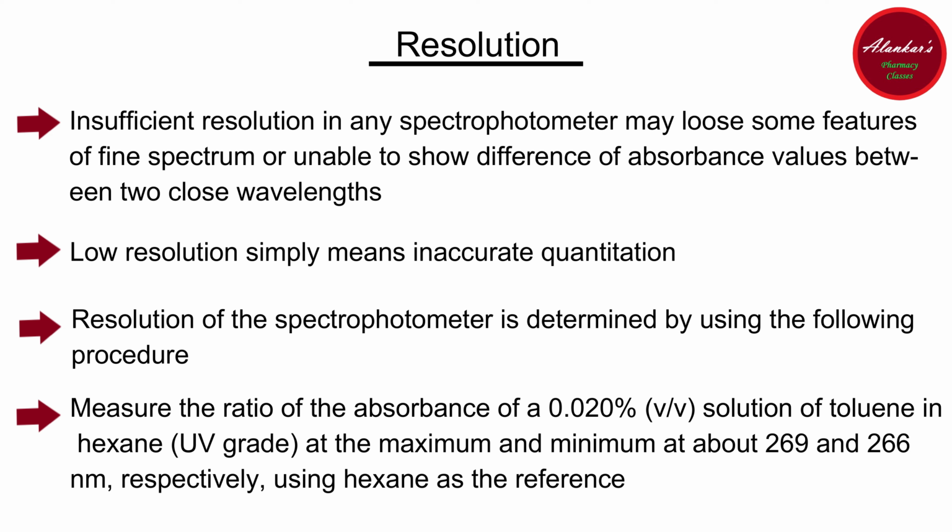Now the next test is the resolution. Insufficient resolution in any spectrophotometer may lose some features of the fine spectrum or be unable to show the difference of absorbance values between two close wavelengths.